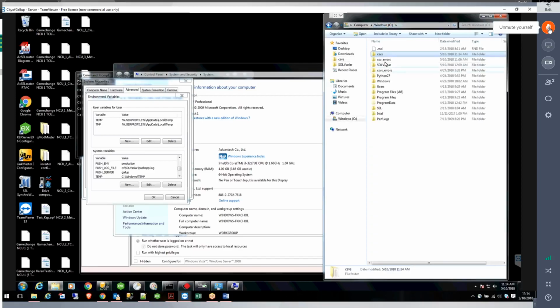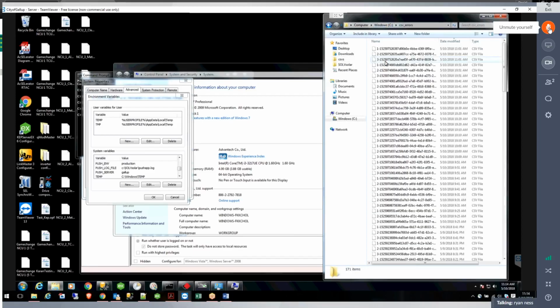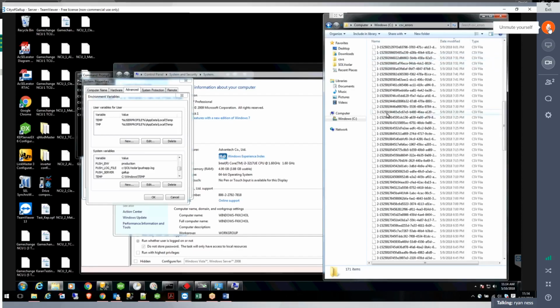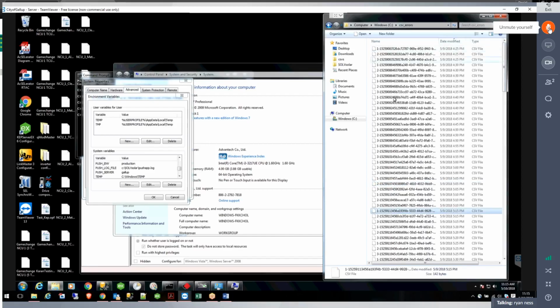I briefly mentioned the errors. The other thing in the telemetry scope is a few files in here, because I think there was an issue at City of Gallup. When we were messing with those Modbus channels and fields, these were getting pushed in error. I don't know if something changed or caused this. But when you went and fixed the channels, and then I went and fixed the data loggers to match the channels again, these stopped. I think that's just these errors stopped. The points have been signed off on, and we're all on the same page, I believe.